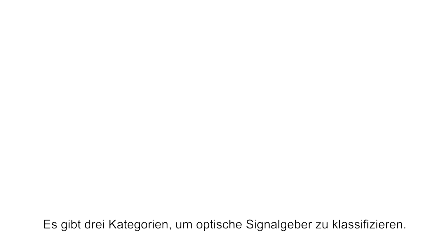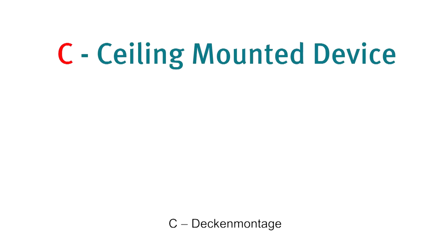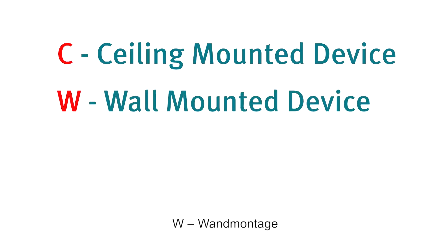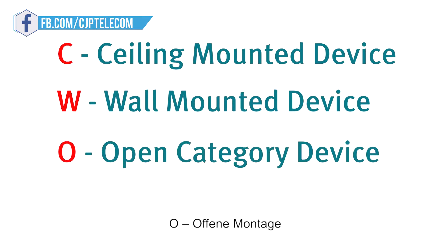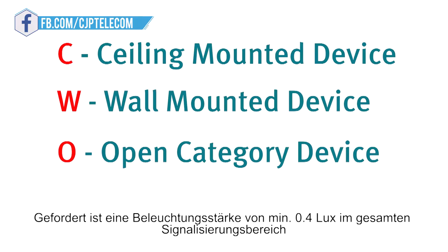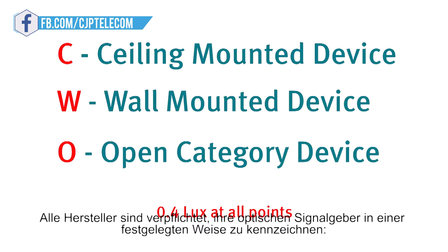There are now three categories that a VAD can be rated under: C for ceiling mounted device, W for wall mounted device, and O for open category device. The specified output for a VAD is now required to be 0.4 lux at all points within the specified coverage volume, and all manufacturers are now required to label their VADs in a specific way.